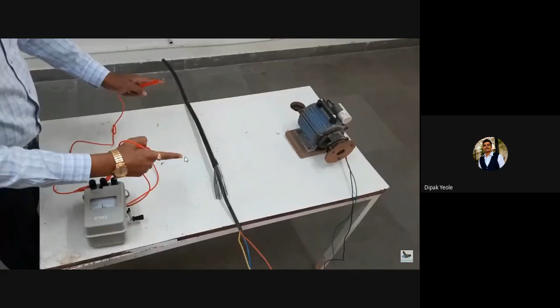Now we are interested in our second electrical equipment, and here you can see this is the power cable. The voltage range this power cable carries is about 1100 volt. We have to connect this power cable with our mega ohm meter, the connection being the same as previously: the line terminal connects to the conductor terminal, and the earth terminal connects to the body or insulating material of the electrical cable.